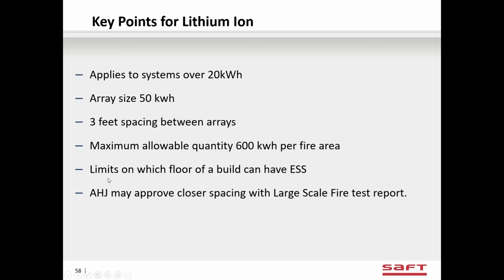They put some limits on which floor of the building you can put it in because they want the fire trucks to be able to access it. So there's a limit of 75 feet above grade and 30 feet below grade. And then they have this proviso that says the AHJ, or the authority having jurisdiction, can approve closer spacing if they have a large scale fire test report. So now we're going to get to that large scale fire test.